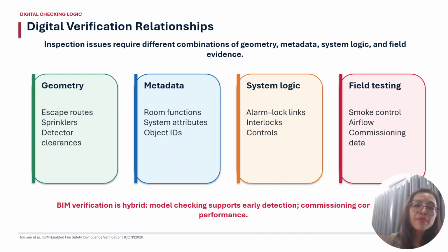So the digital verification relationship is that inspection still requires a different combination of geometry, metadata, system logic, and field evidence. In geometry: escape routes, sprinklers, detector clearances. In metadata: room function, system attributes, object IDs. In system logic: alarm-lock links, interlocks, controls. And in field testing: smoke control, airflow, commissioning data. So BIM verification is hybrid. Model checking supports early detection, while commissioning supports coordination and performance.